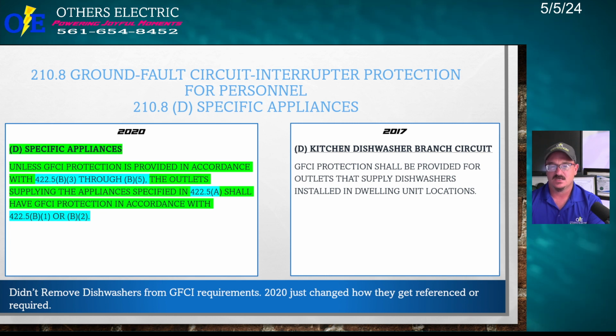Okay? The 2017 said D, kitchen dishwasher branch circuit. It used to say the dishwasher had to be GFCI protected. Now the code says specific appliances, and we're going to get into those specific appliances, okay? So they didn't remove dishwashers from the GFI requirements, just changed how they get referenced, okay? Didn't remove dishwashers, just changed how they told you that dishwashers were required. So let's take a look at this.